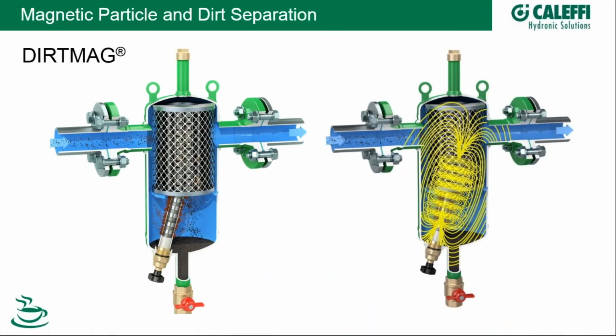it worked fine. So that's why manufacturers have, well, at least in Caleffi's case, magnetic separators that, in addition to non-magnetic dirt separation, also do magnetic dirt separation. And you can see what's happening here. We have a specially designed separator with a stack of rare earth magnets stacked on top of one another. These are called neodymium iron boron. And this stack is inside of a brass sleeve up into the belly of the separator.